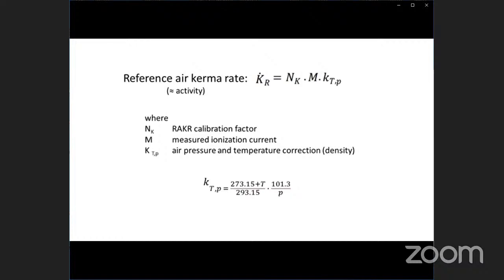The first one is the calibration factor. The second one is the measured ionization current. And the third one is the air pressure and temperature correction. Because inside the well-type chamber, the air density can be different according to the pressure and temperature. That's why we have to calculate at the time of measurement this correction factor.